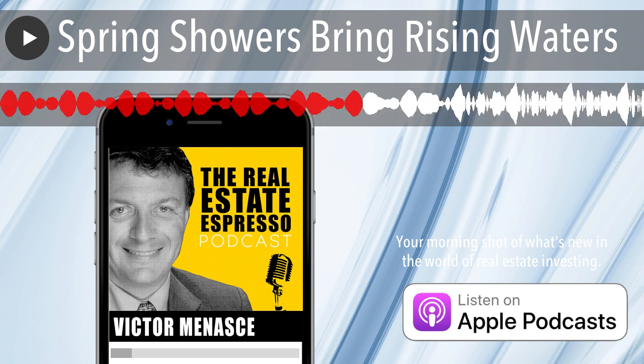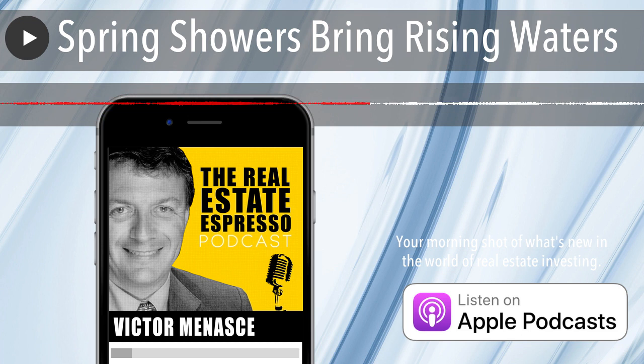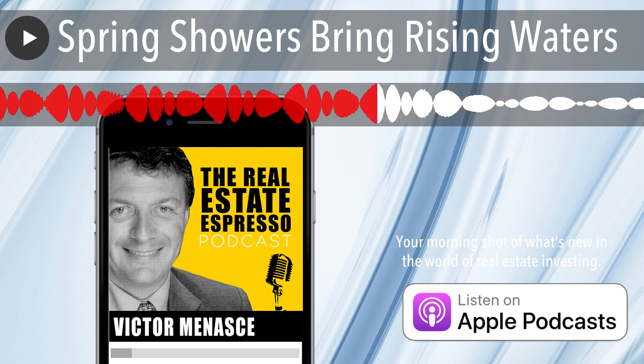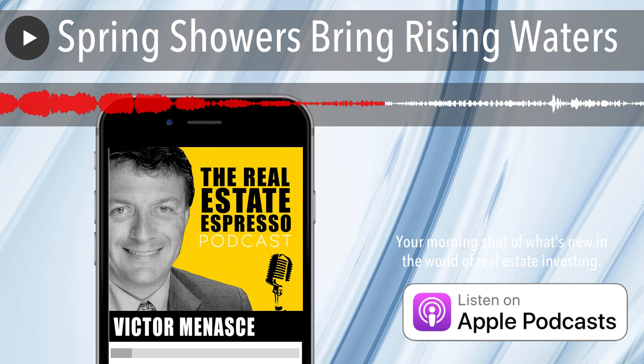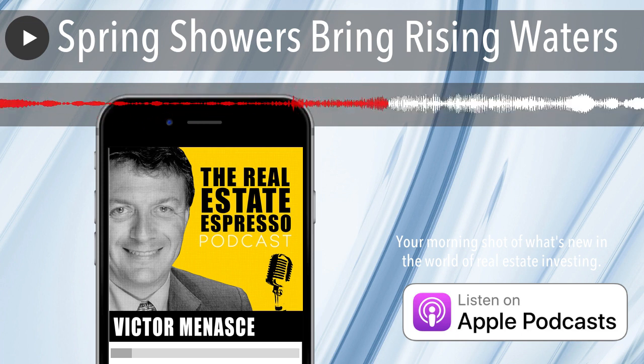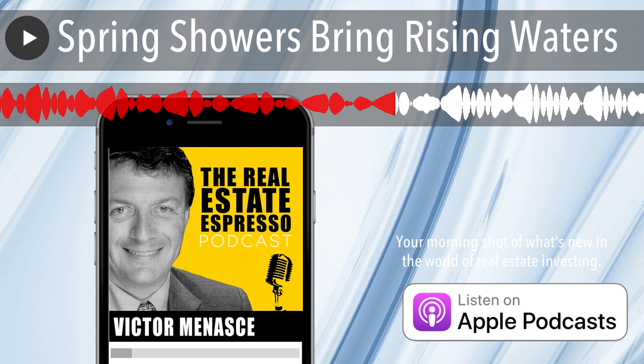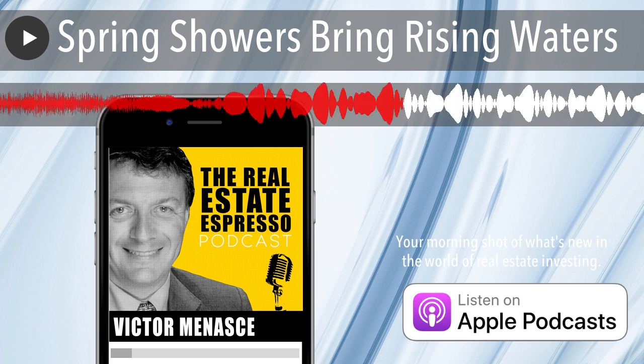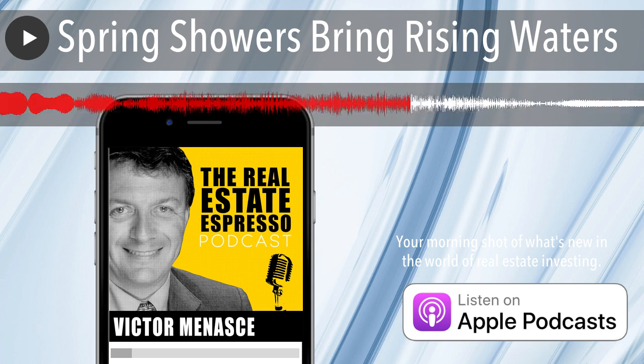I highly recommend a high water alarm to be placed in the sump pit in your basement. That alarm should also have a battery backup with a battery life of at least a few days. Some home alarm systems also have a battery backup, and you can often add a water sensor to the alarm. That way, the alarm monitoring service will at least get notified of the high water alarm before you've got a full flood on your hands. And some modern alarm systems use a cellular connection in case your internet is down.